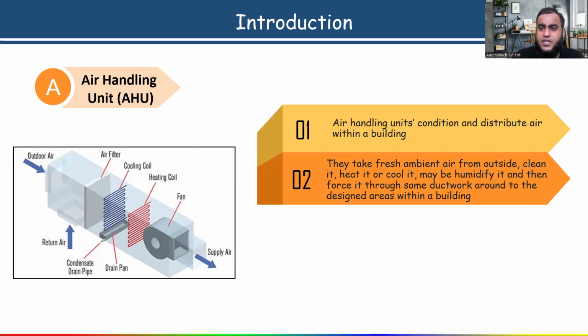It depends on which type of space. Like in healthcare facilities, we have operating rooms and patient rooms, so it depends on the space. All this you will get from, suppose you want to know how much relative humidity we have to maintain. So remember, as per ASHRAE, the American Society of Heating, Refrigeration and Air Conditioning Engineers, always for human comfort, inside the room, we have to maintain 50 to 55% humidity.